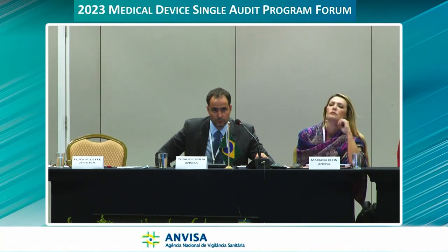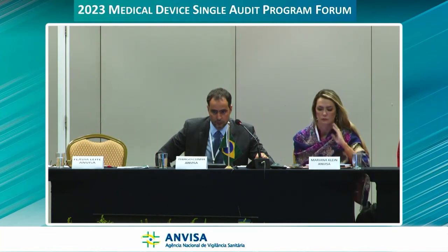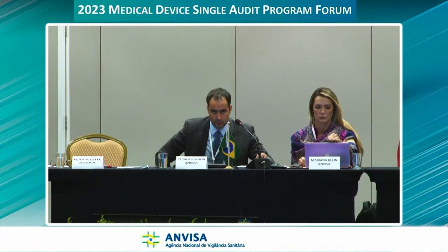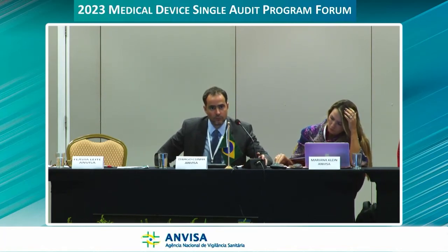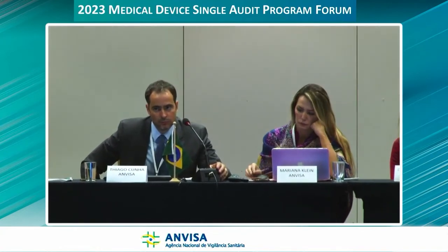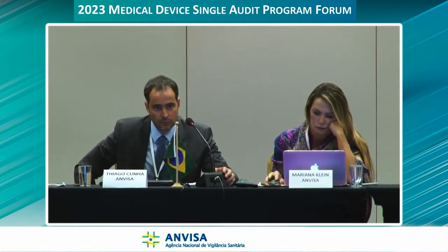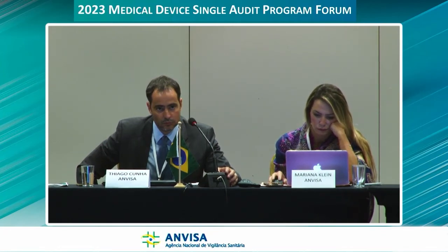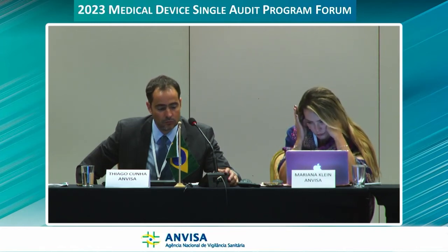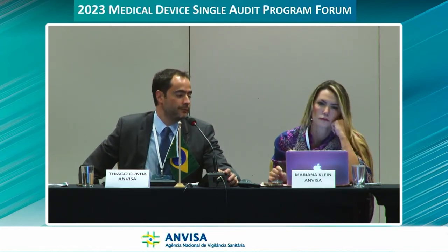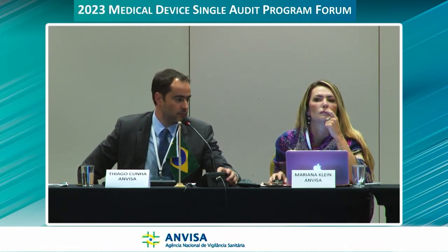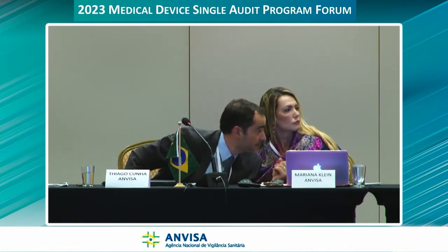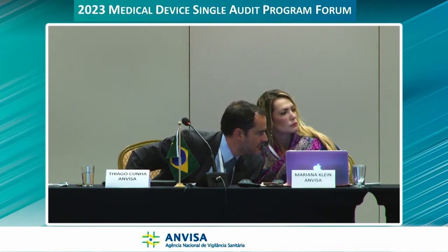like in Japan, where class 2 and some of the class 3 are approved by RCBs, others by PMDA. We have the EU approach where everything is given to the notified body. So is there any discussion ongoing to harmonize also on product related approvals? Because I would say that on a QMS basis, we are in quite good standing with MDSAP. It's a mature program, very successful. And so my question is exactly this: any plan for harmonized product approval?